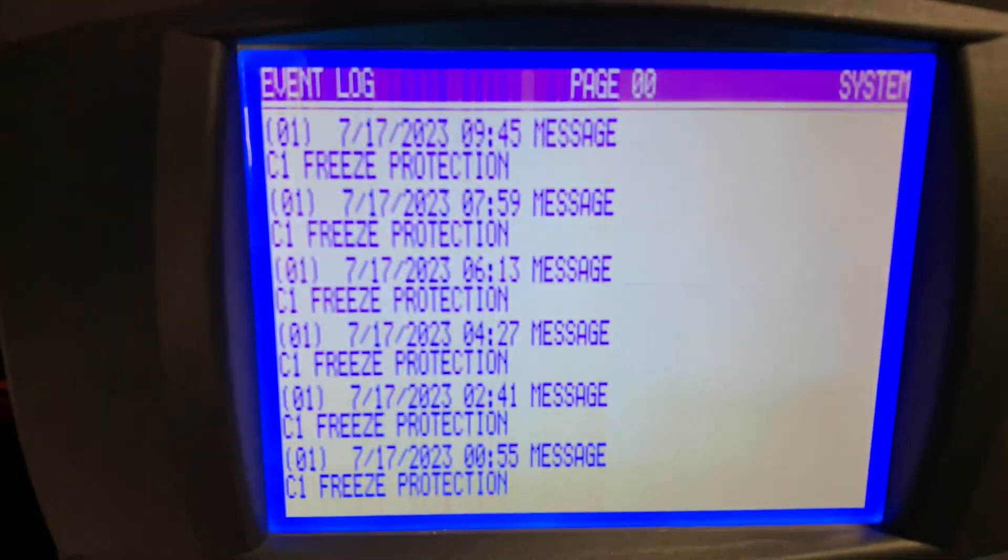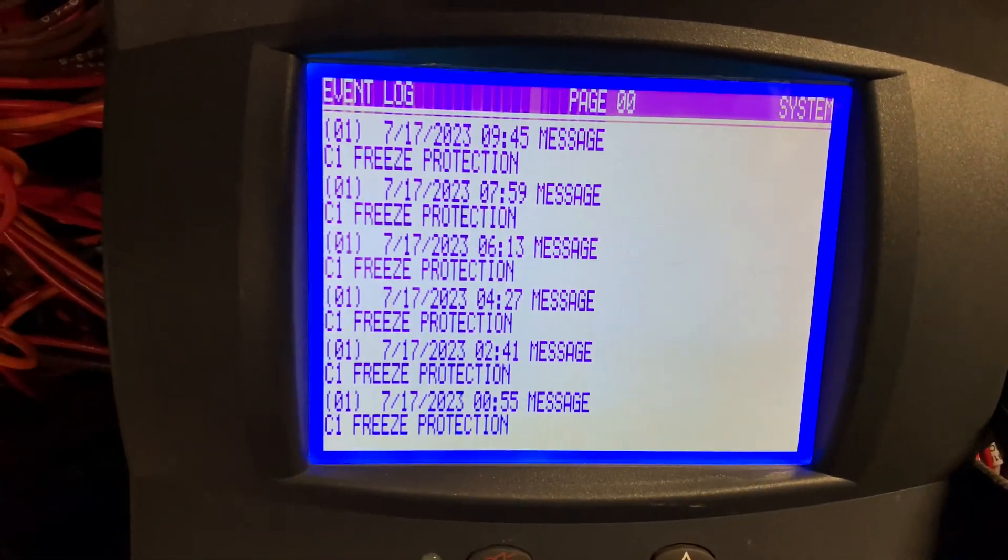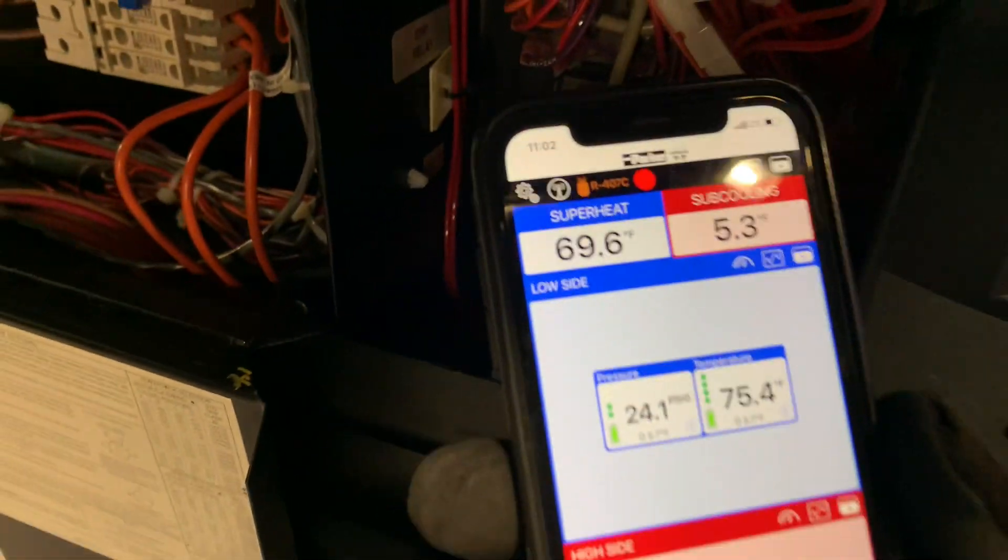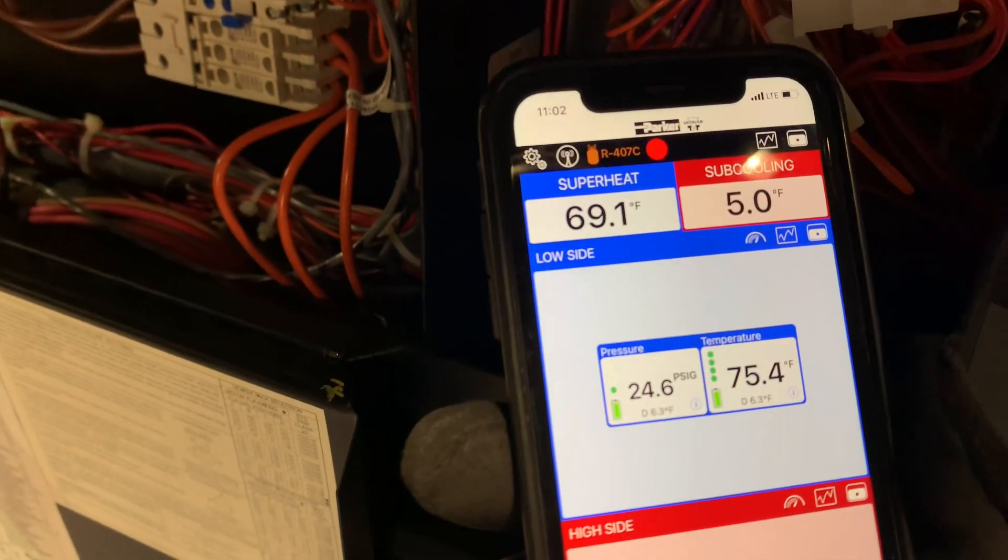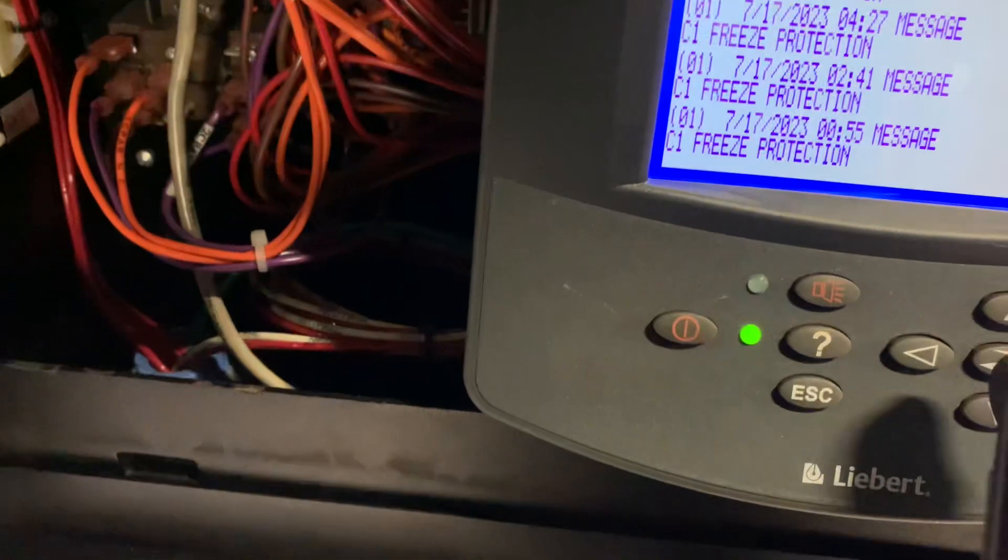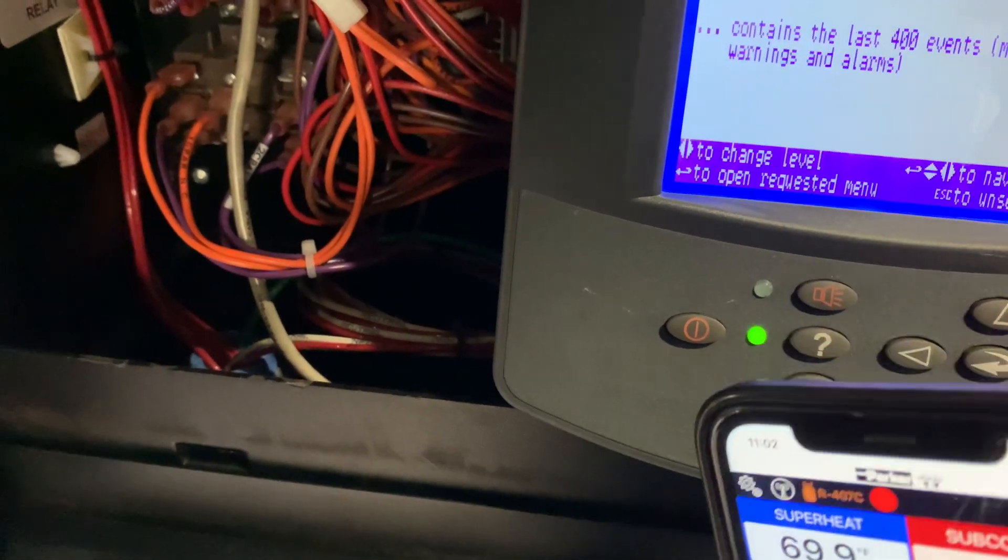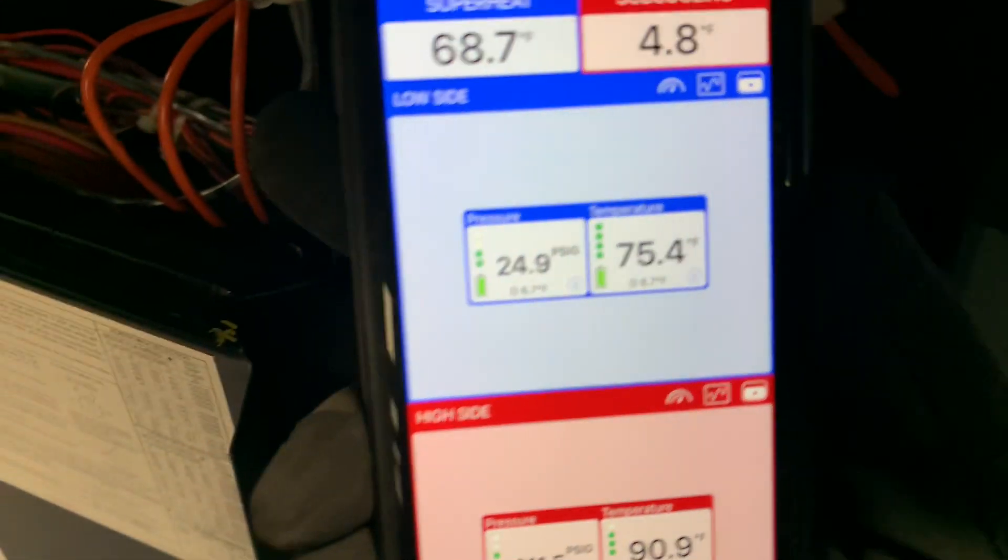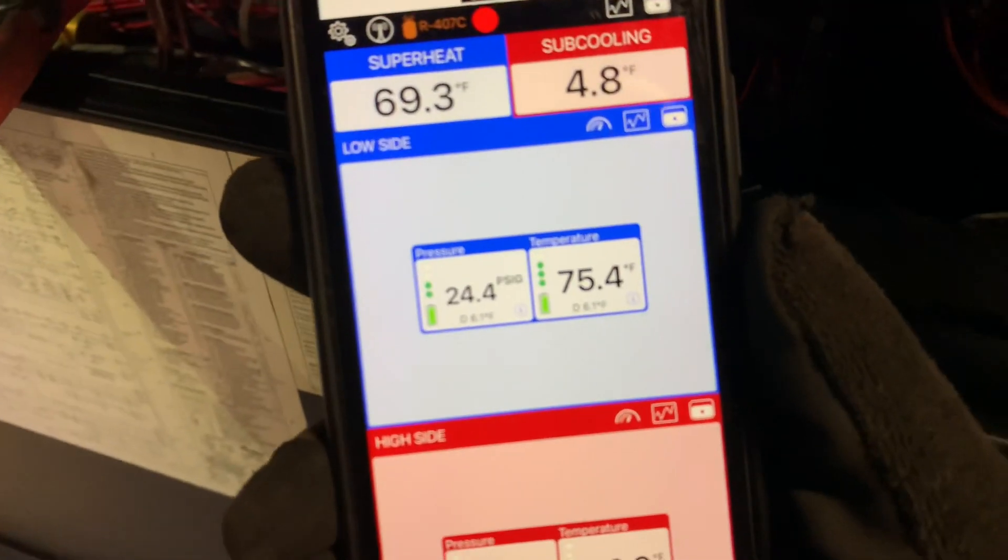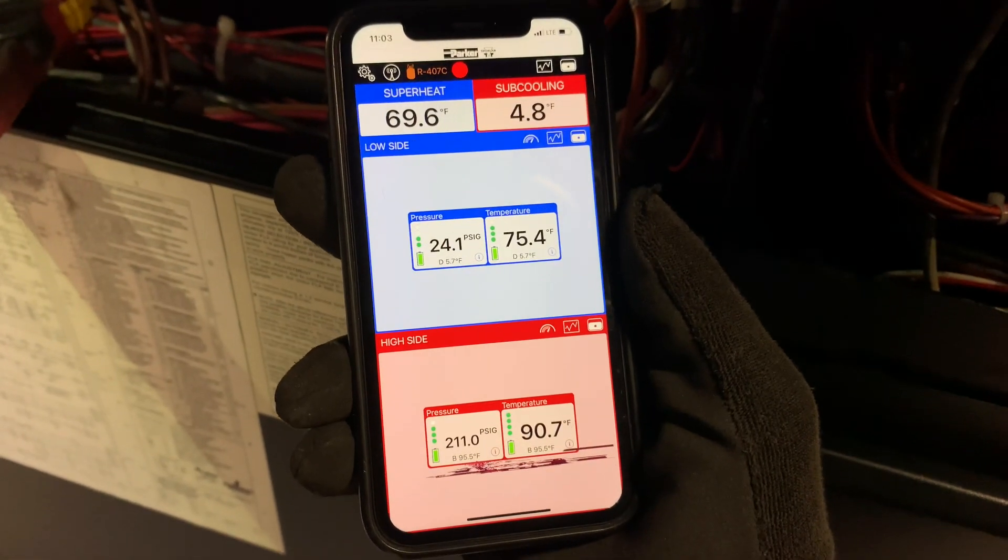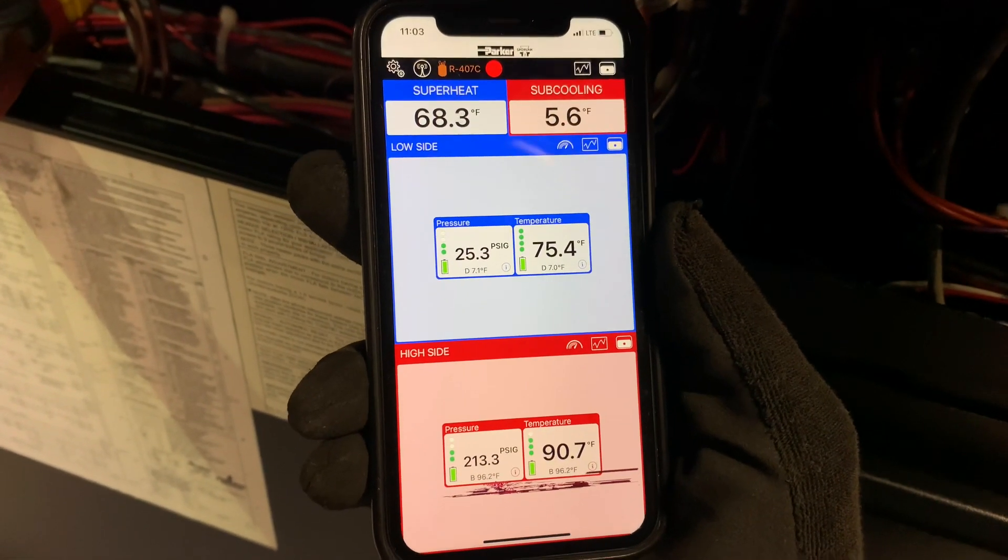I'm going to go ahead and add some refrigerant. Now, before you go ahead, if you have a situation like this, a bad TXV, or a restriction, would give you the same warning. So, make sure you do your due diligence first. Check your superheat and subcooling readings, like I'm doing right here. You can see my superheat is very high, the subcooling is very low.